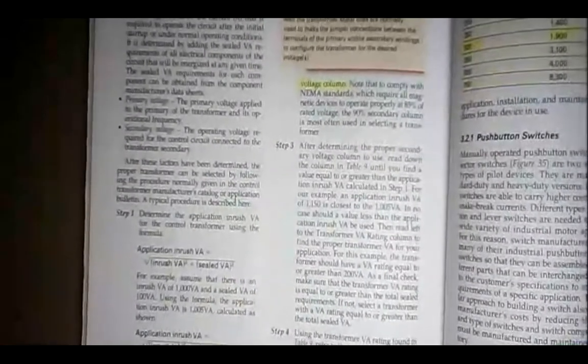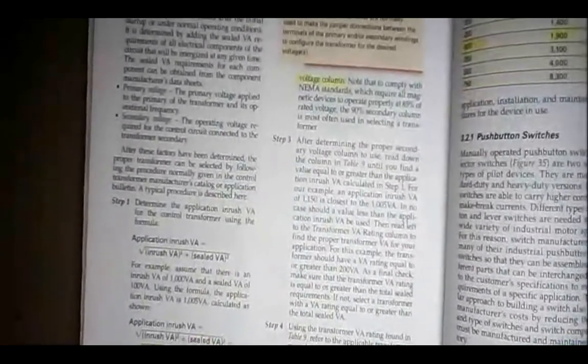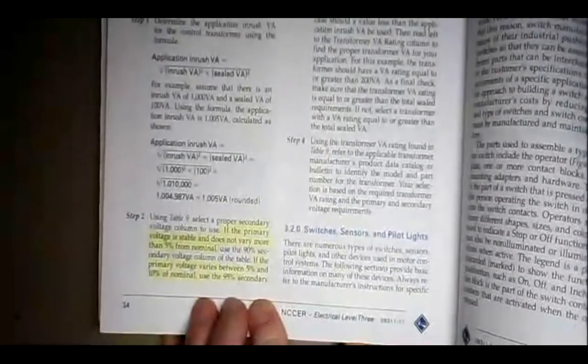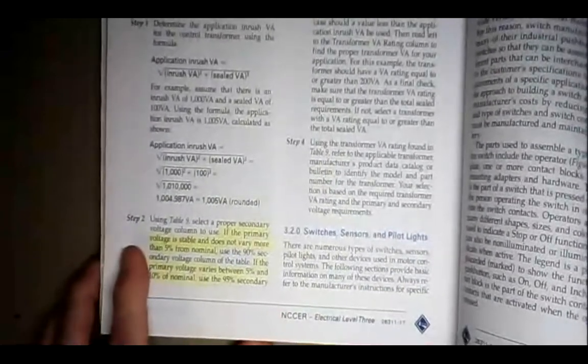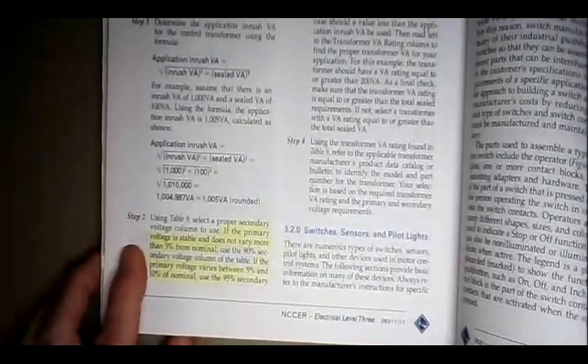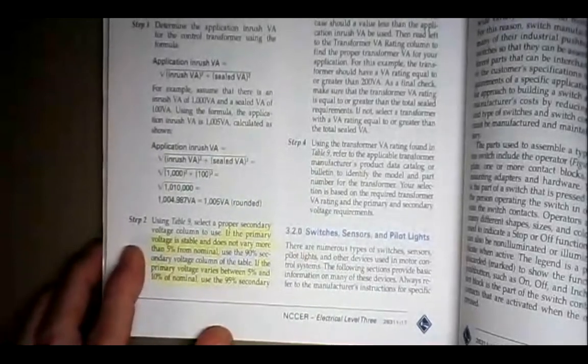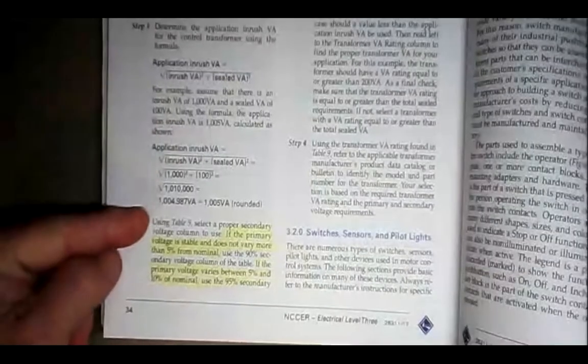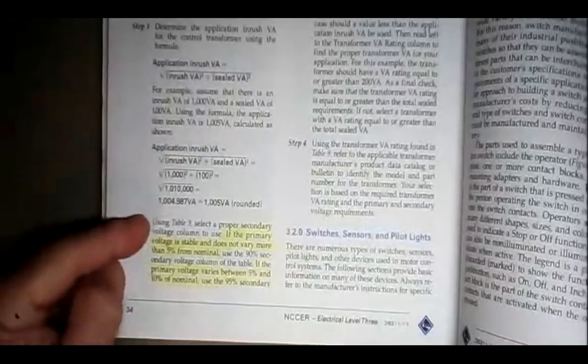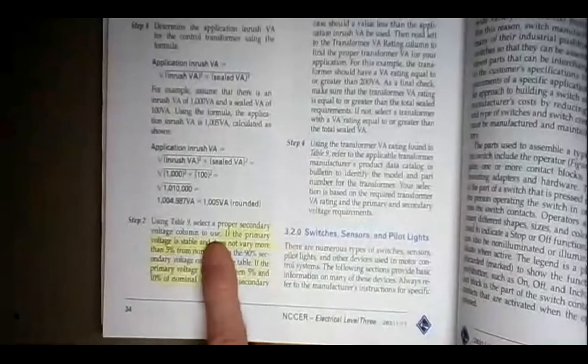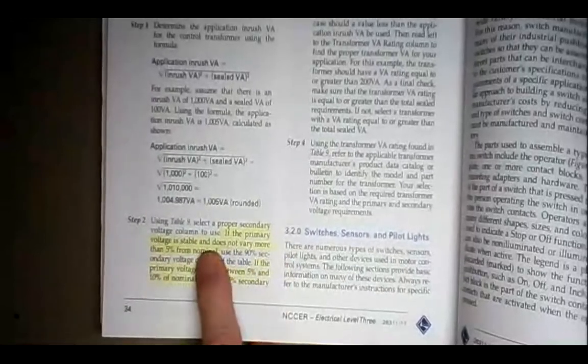Over on page 34, at the very bottom of the page, step 2. It says, after the factors have been determined, the proper transformer can be selected by following the procedure normally given in the control transformer manufacturer's catalog application bulletin. And here they're talking about what you do in step 1. You find the inrush current. It says, using table 9, select a proper secondary voltage column to use.